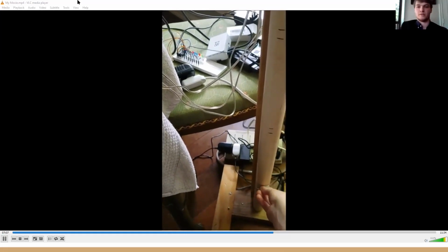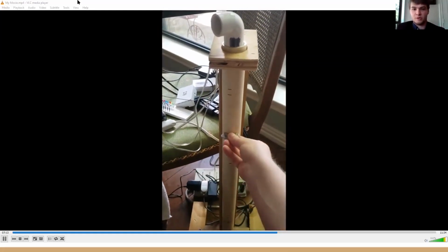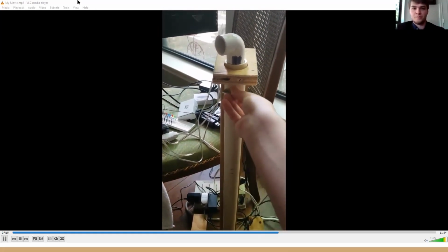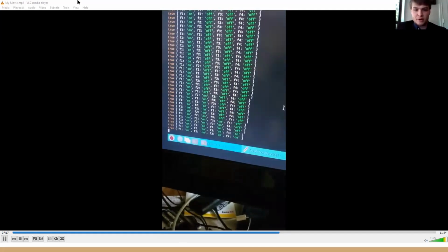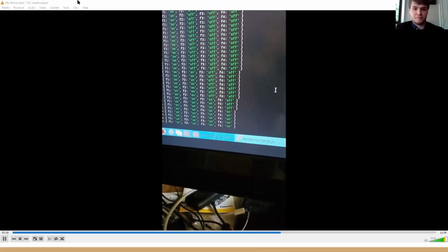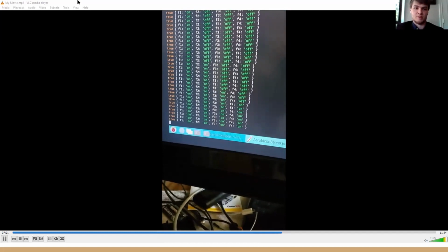F4 is the top float. Like I was trying to say earlier, we want to have a float above F4 that's independent, has its own circuit to turn on the pump. We just went past F2, it turns on. We just went past F3 and F4, and they turn on respectively. And you can keep seeing that by the console.